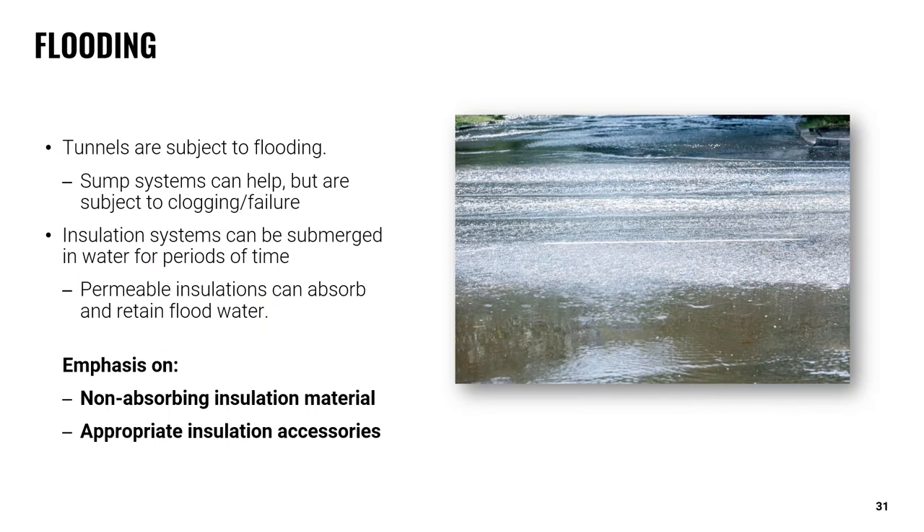Another challenge with underground tunnels involves the risk for flooding, which is quite common for tunnels to experience at some point within their lifespan. If flooding occurs, your insulation system could be submerged in water for periods at a time. If a permeable or absorbent insulation material is used, water could penetrate through any openings in the vapor barrier, saturating the insulation and compromising thermal resistance. Some sump systems can help mitigate this risk, but they themselves are subject to clogging and failure. A non-absorbing insulation may be preferred as it will resist absorbing water even in the event of a flood. It's equally important to use proper insulation accessories to ensure the integrity of all joints and penetrations.